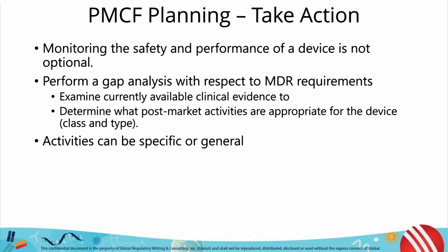Now that we know that we need a plan for the PMCF, the first step is to determine what kind of activities are needed. For this, you'll want to perform a gap analysis with respect to MDR requirements. You'll want to examine currently available clinical evidence to determine what post-market activities are appropriate for the device class and type. If current post-market data on the device is not adequately comprehensive, new data may need to be generated, even if the devices are well established and have been on the market for several decades. This enables an evaluation of their safety and clinical performance in relation to an evolving state of the art.